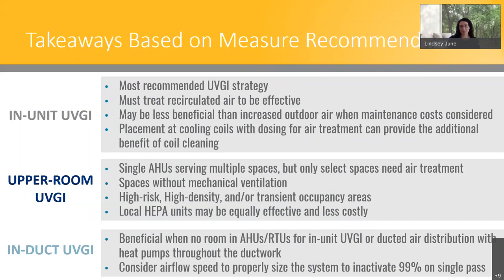And finally, strategic placement in air handling units can also provide an added benefit of coil cleaning for additional energy savings. So facing the UVGI towards the wetted surfaces like cooling coils or drain pans can prevent biofilm buildup and increase heat transfer and energy efficiency.